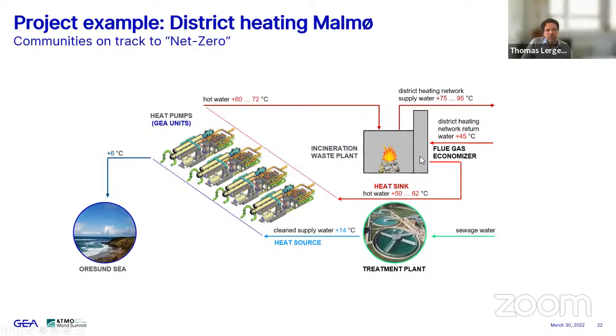This incineration plant, if at some point it might get switched off or removed or replaced, we now have the technologies to also do preheating by 10 Kelvin on the low temperature side. And now, especially with the highly efficient piston compressors, we've also seen we can come up to 95 degrees Celsius. So even that step we can now do with heat pumps. And it's not unusual that these projects have a follow-up stage in a couple of years.